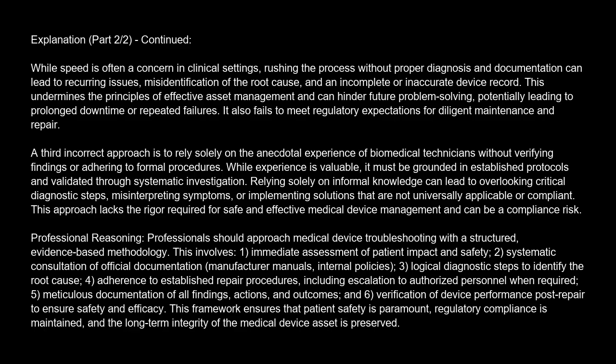Professional reasoning. Professionals should approach medical device troubleshooting with a structured, evidence-based methodology. This involves: 1. Immediate assessment of patient impact and safety. 2. Systematic consultation of official documentation, manufacturer manuals, and internal policies. 3. Logical diagnostic steps to identify the root cause. 4. Adherence to established repair procedures, including escalation to authorized personnel when required. 5. Meticulous documentation of all findings, actions, and outcomes. And 6. Verification of device performance post-repair to ensure safety and efficacy.